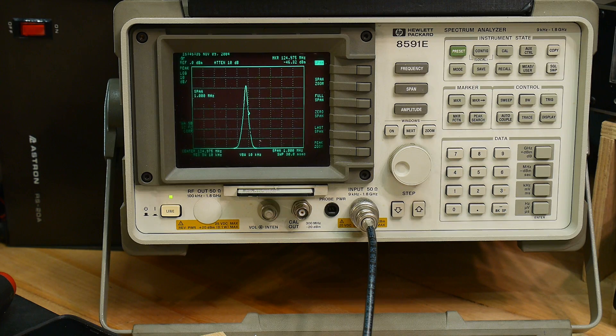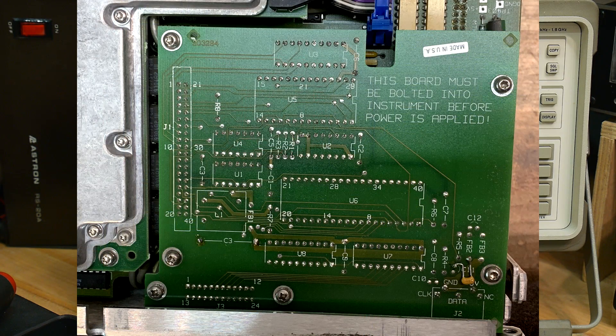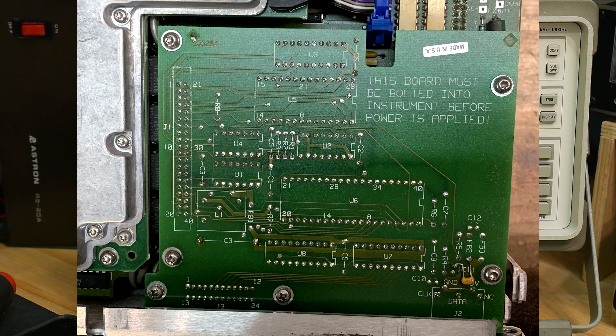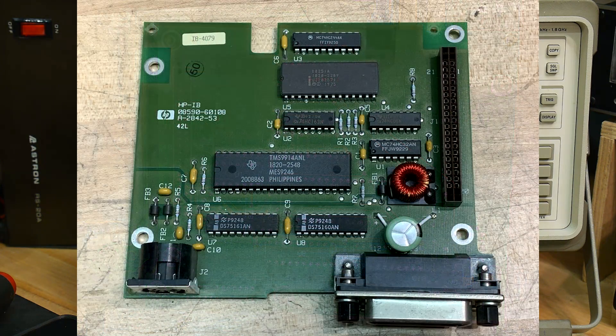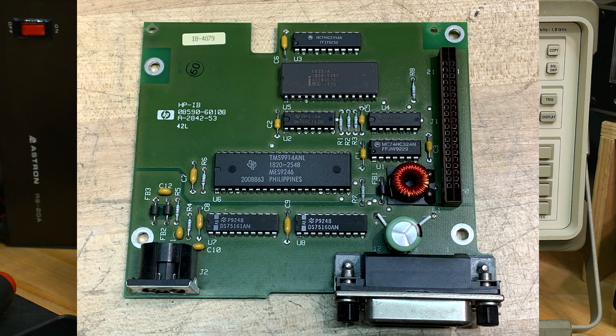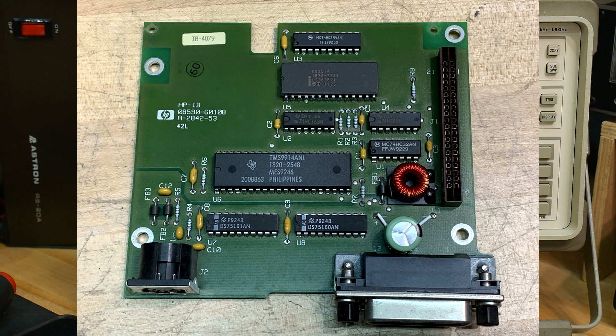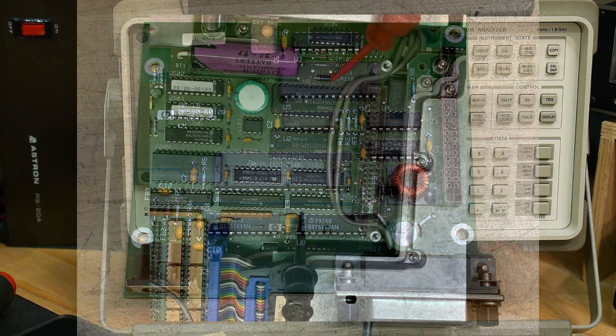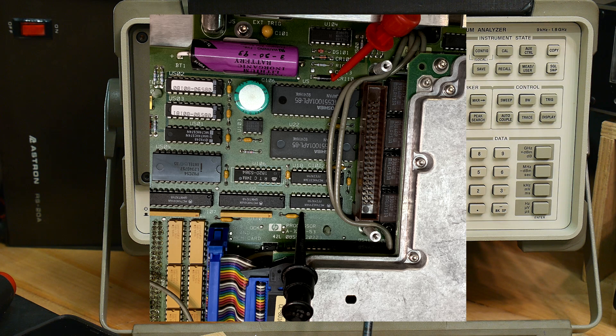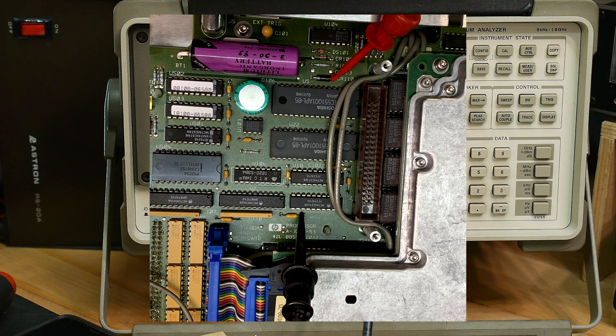So you take the case off, and the first thing you need to remove is a little board that contains the HPIB interface. It's actually HPIB plus keyboard. You can actually hook a keyboard up to this thing. I think it's an old IBM XT keyboard, if I remember right. You take out that card, and then you can see the battery underneath. There is a battery cell, and there actually is a super cap also, so when you change the battery, supposedly the super cap keeps everything good while you swap out the battery, but I didn't trust that.